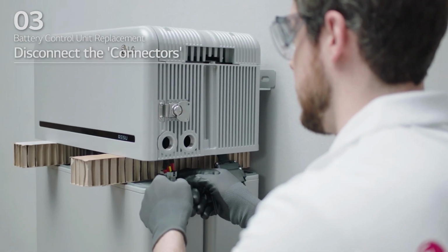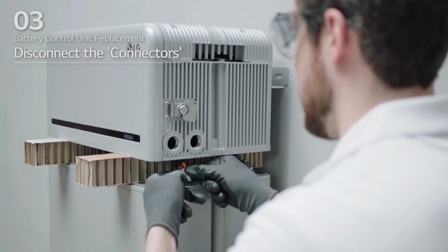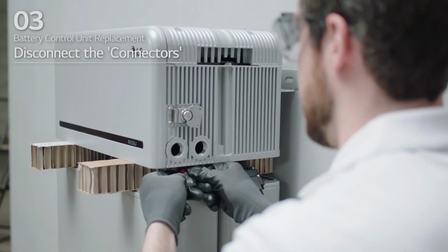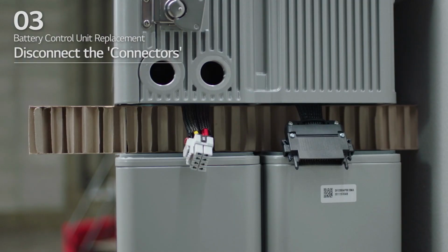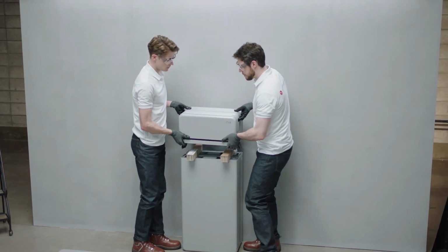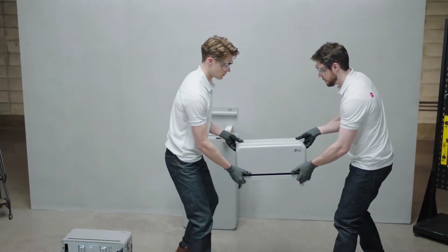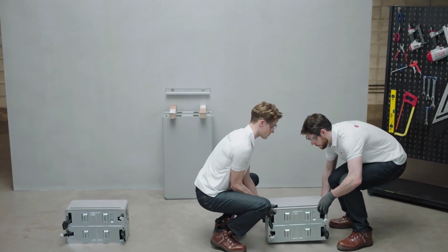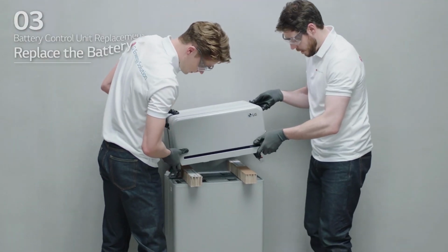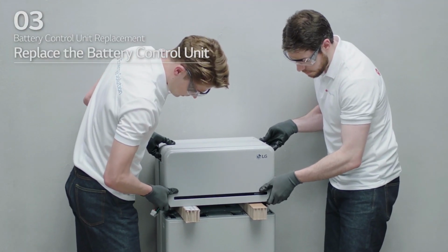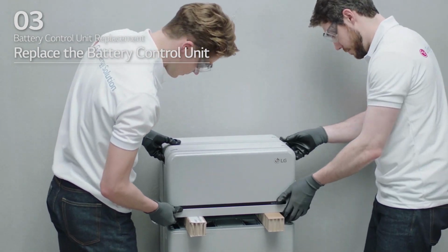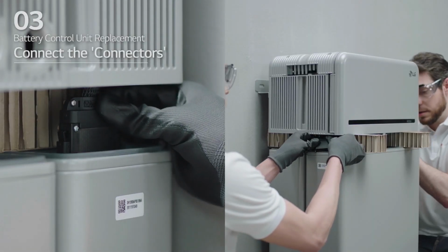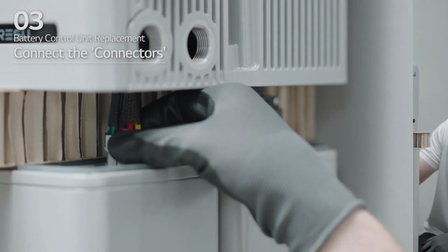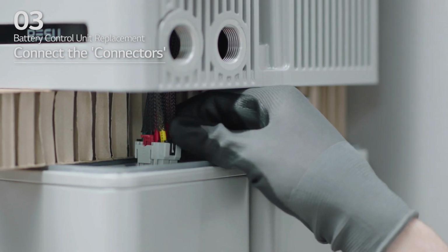To remove the sensor connector, push in the sides of the connector and pull out the connector vertically. Then, pull the connector out to the side of the battery module. Replace the battery control unit and align with the battery module. Then, connect the 2 power connectors and 2 sensing connectors until you hear a click.